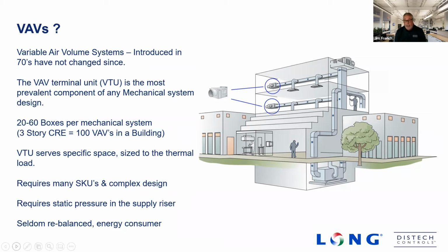They initially came to be to replace constant volume systems as a more energy efficient design. With the thought behind it, they can vary the airflow into the space for heating and cooling purposes based on the load. And as the load decreases in the building, you can back off on the fan horsepower, creating that variable airflow.